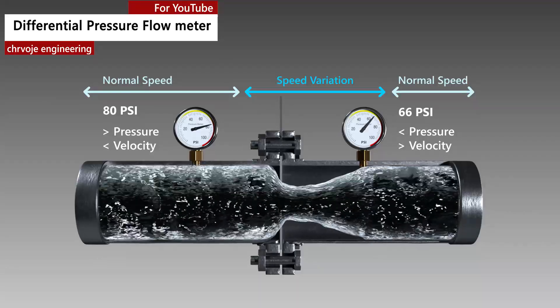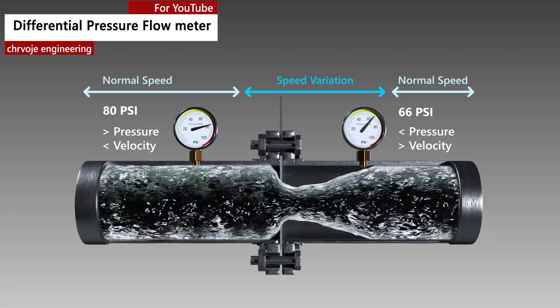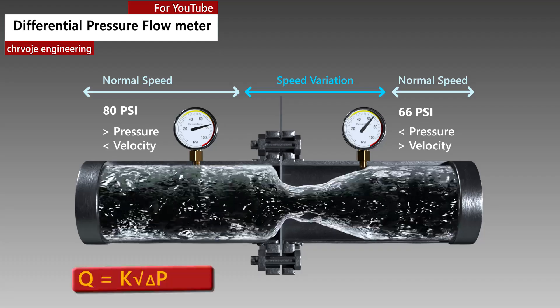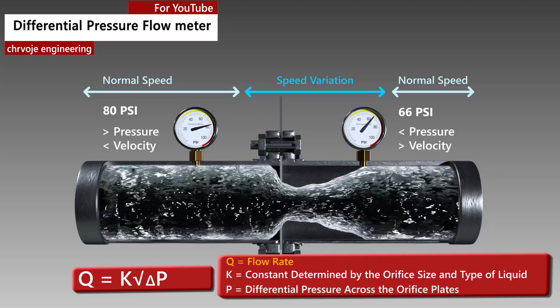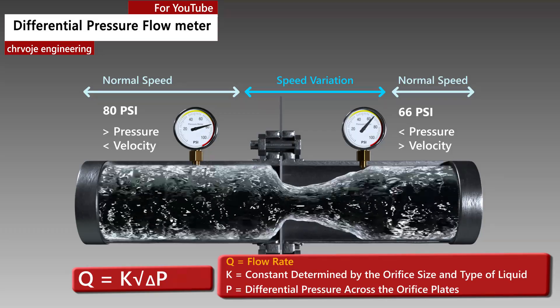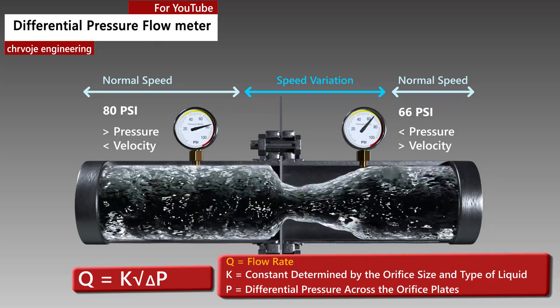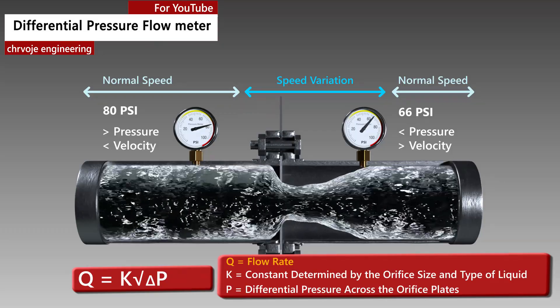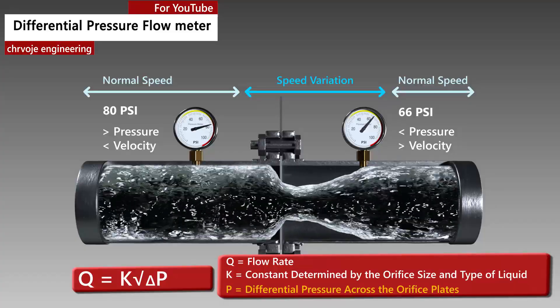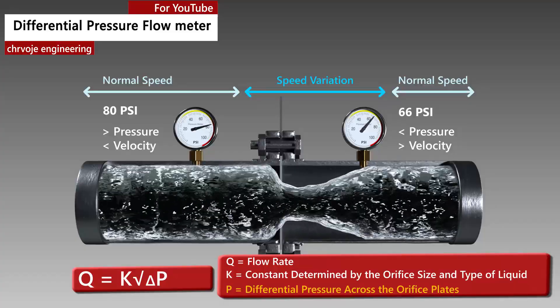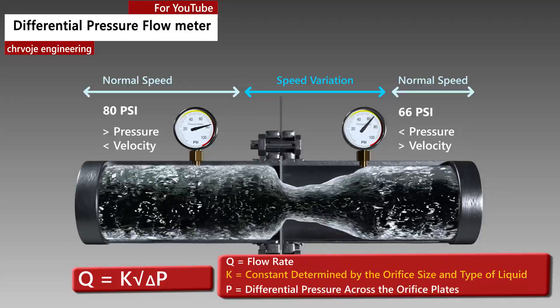With a known differential pressure and velocity of the fluid, the volumetric flow rate can be determined. The flow rate q of a fluid through an orifice plate increases in proportion to the square root of the pressure difference on each side multiplied by the k factor.